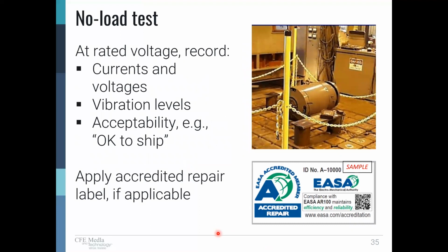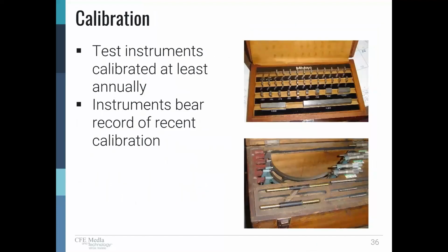We reach the no load test. The machine's been assembled. We measure the voltages and currents at no load, vibration levels, and check the mechanical condition. When the job is done and someone's done all these tests, they say it's now okay to ship. Somebody has to say, this motor's ready to go. And then we apply the accredited repair label if applicable. So if it's an accredited repair service center, then they put the label on the motor saying, this is an accredited repair. We've maintained the efficiency on this motor.